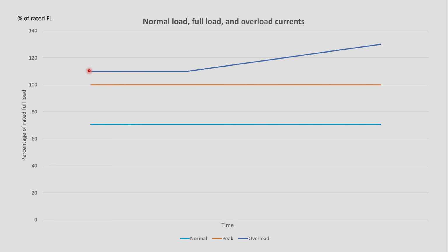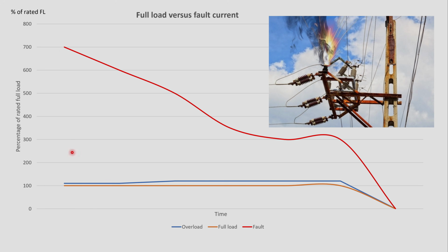It won't break the inverter, but the inverter is now overloaded. So usually 10% is an overload, 20%, even 30%, depends on the application. But a fault tends to look more like this. Its current is excessive. That's a fault, the red line here. So what we notice with a fault is a very high current that rapidly grows, and it tends to be many times higher than the load current. So the full load current maybe is 100%, but a fault would be 4 times that, 5 times that, 6 times. Okay, but it does really depend on the application.